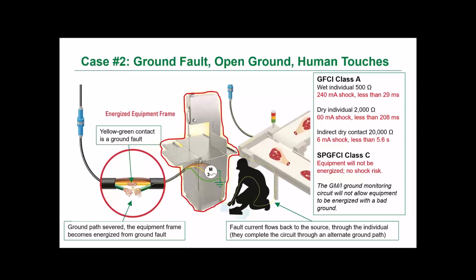Now, on the Class C special purpose GFCI side, again, in this case, the equipment would not even have been allowed to be energized, as the ground monitor interrupter circuit would detect the severed ground and not allow the equipment to be started. So again, the proactive nature of that ground monitor would have removed the possibility of someone even touching the equipment to receive a shock.